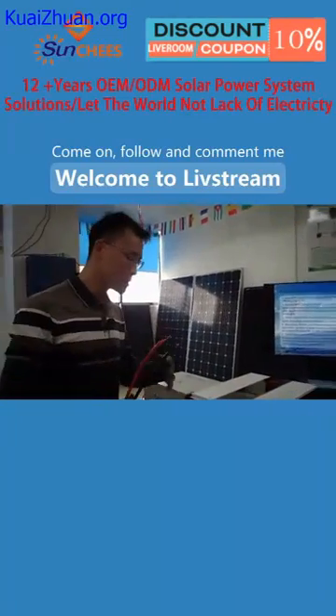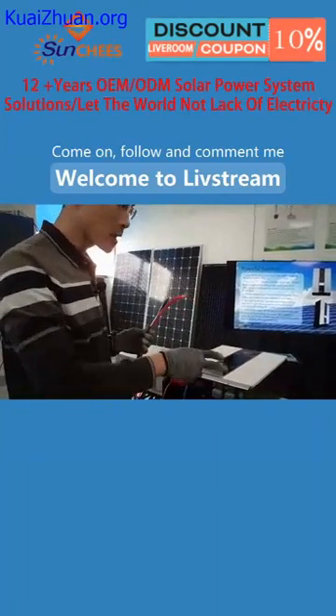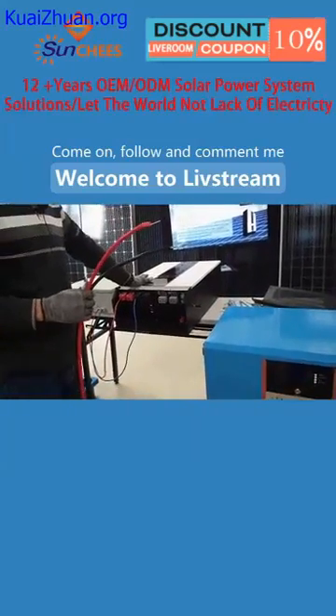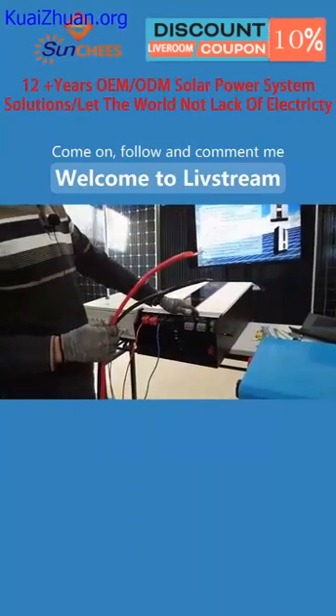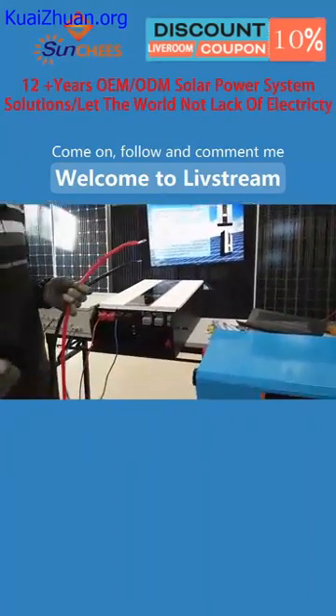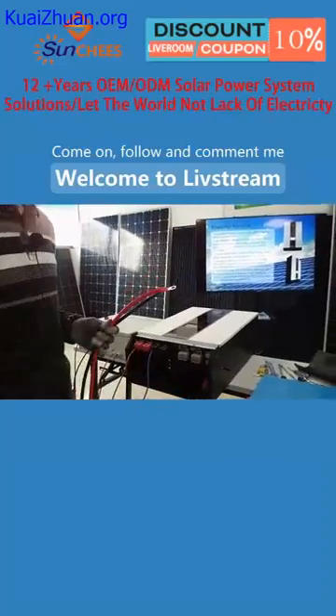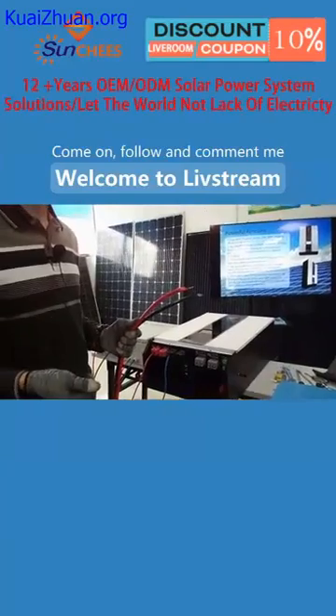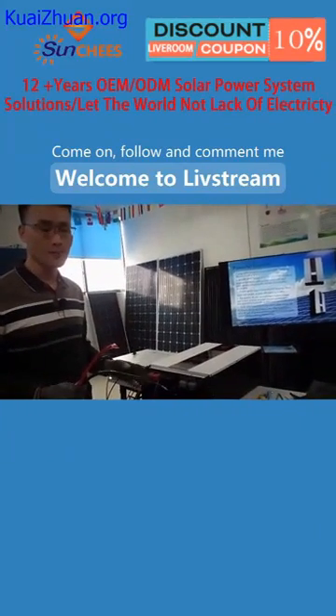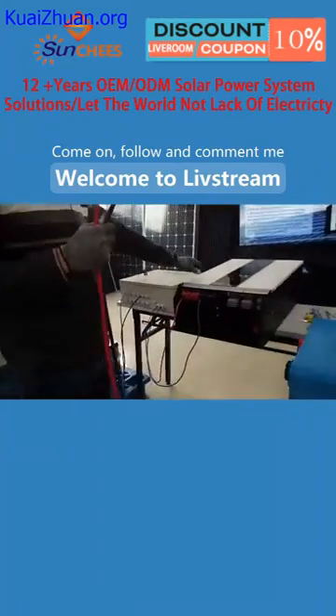But when you do the installation, you need to make sure you choose the right size of the cables, because normally the current between the battery bank and the hybrid inverter is big. For example, for our 6 kilowatt hybrid inverter, when the inverter is working at full power, the current between the battery bank and the hybrid inverter is more than 100 ampere. So you need to choose big size cables to connect them. But don't worry about that, because if you buy the complete set solar power system from our company, we will provide all the necessary cables you need to install the solar power system. For example, the battery cables, the PV cables and the cables between the PV combiner and hybrid inverter.